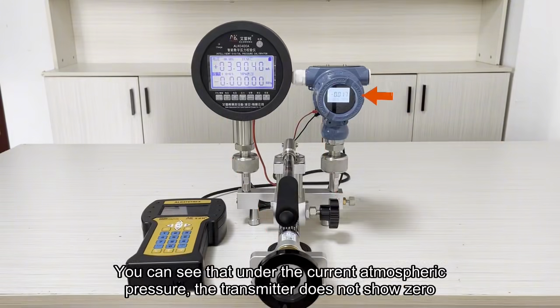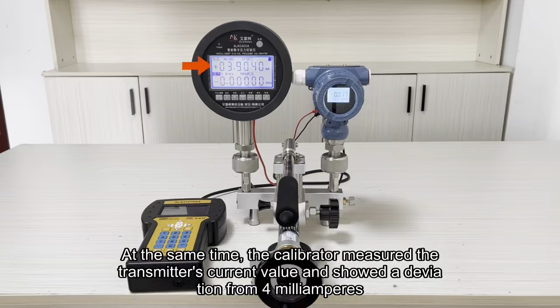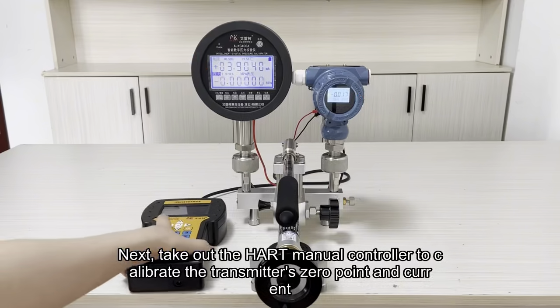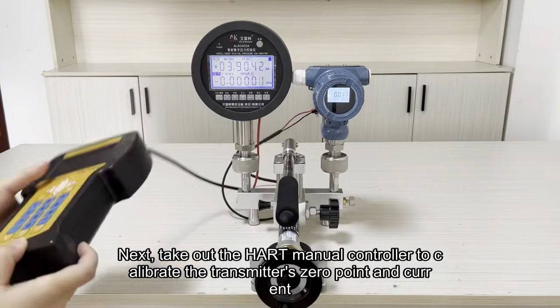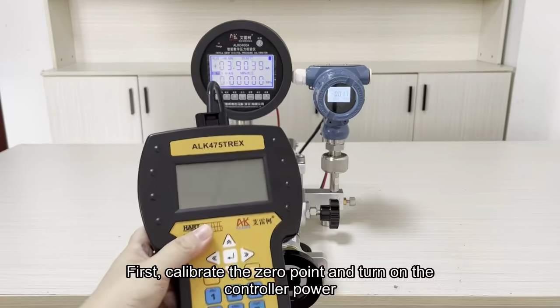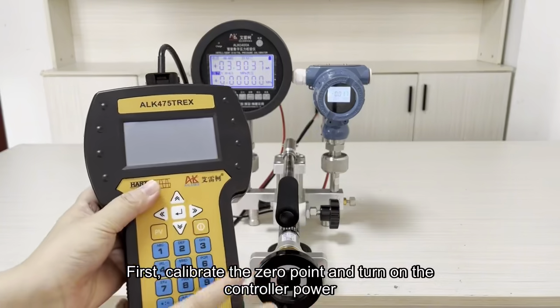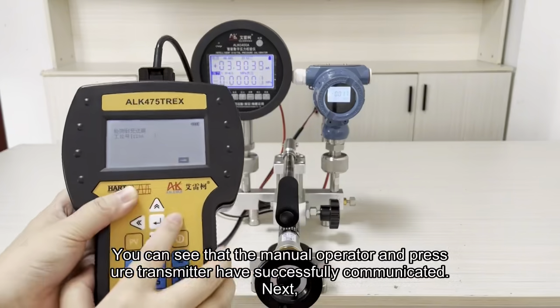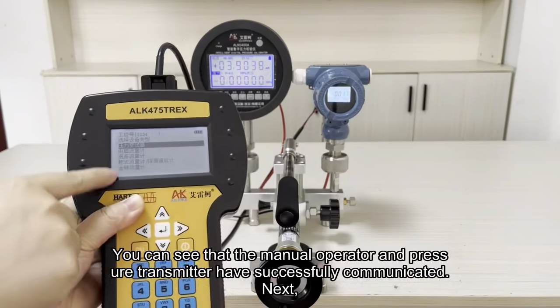You can see that under the current atmospheric pressure, the transmitter does not show 0. At the same time, the calibrator measured the transmitter's current value and showed a deviation from 4 mA. Next, take out the HART manual controller to calibrate the transmitter's 0 point and current. First, calibrate the 0 point and turn on the controller power. You can see that the manual operator and pressure transmitter have successfully communicated.